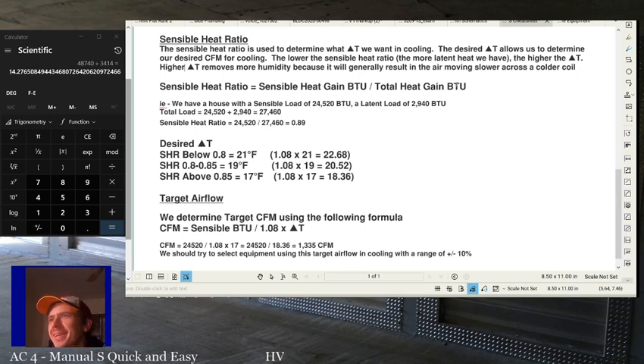All right. So the lower the sensible heat ratio, the more latent heat we have, the higher the delta T. Higher delta T removes more humidity because it will generally result in the air moving slower across a colder coil. All right. So our sensible heat ratio equals our sensible heat gain BTUs divided by our total heat gain BTUs. So our sensible cooling load divided by our total cooling load.